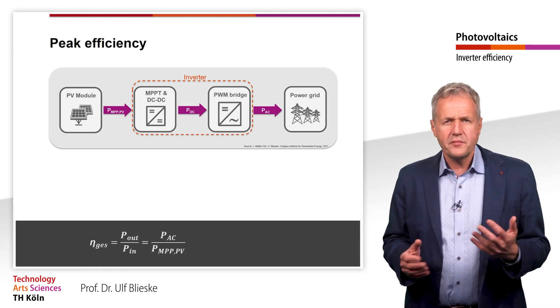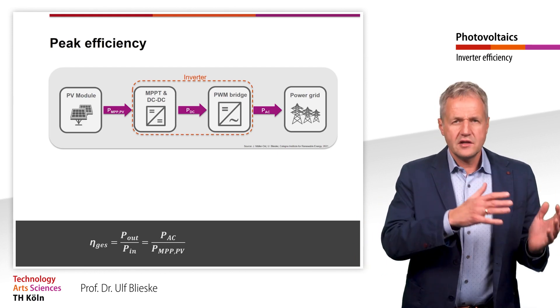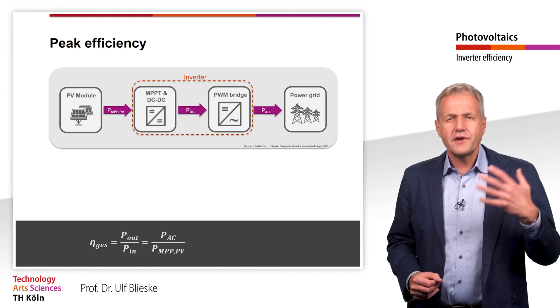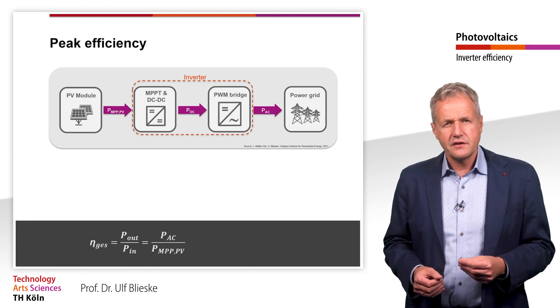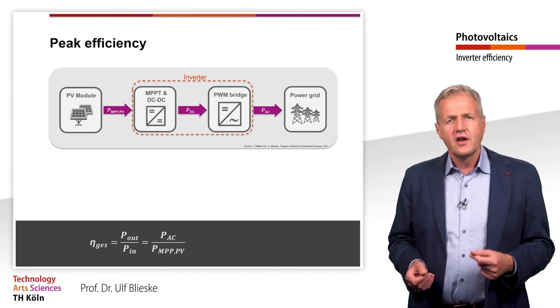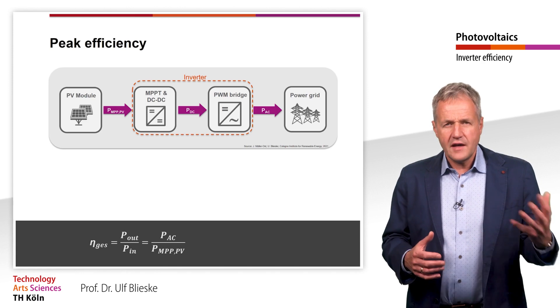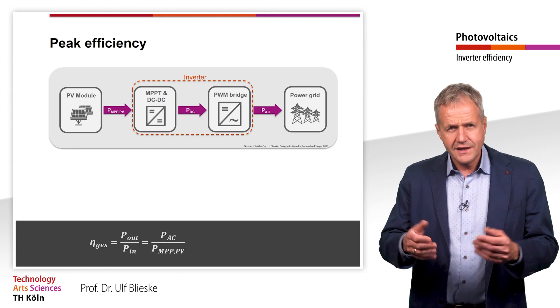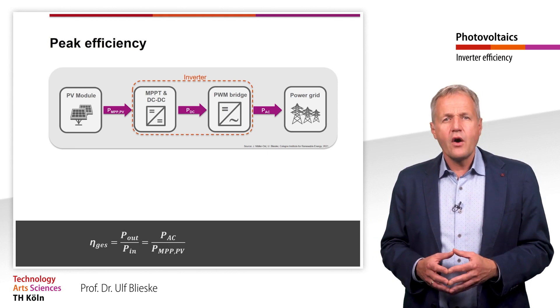The efficiency is the ratio of the power at the inverter output to the power at the input. The input power here is the instantaneous theoretical MPP power of the PV generator. As we have seen, the inverter performs two main functions: finding the optimal operating point — that is the MPP tracking — and the conversion of direct current into alternating current. Both functions are each described by their own efficiency.